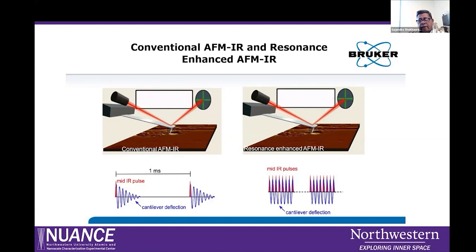But here, the signal intensity may not be that strong, so that's why we have the option of resonance enhanced AFM-IR. We scan the frequency range when there's thermal expansion of the material, and we can find the contact resonance of the cantilever. If we can excite the contact resonance of the cantilever, we can amplify the signal. So there are two ways you can do that, but resonance enhanced AFM-IR is the best option for us because we can amplify the signal.